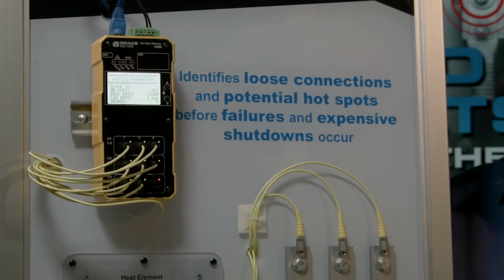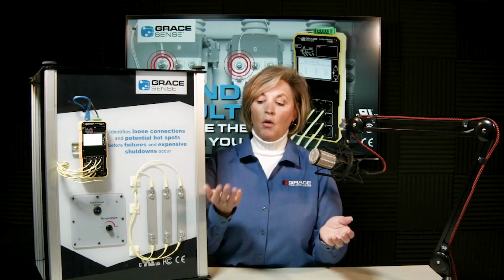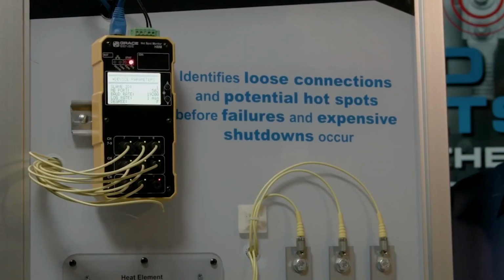Inside the module itself is an internal web page. And inside that internal web page, that's just pinged via an IP address, is where you would do all the setup for if you want to measure temperature in Fahrenheit or Celsius, or change your alarm set points. There are 2 levels of threshold, so you could say one section is for a more critical load, so you'll want perhaps a notification on a lower temperature, and the second set is maybe loads that aren't as critical, and you can raise or adjust those as needed. But the most important thing is to make sure that the alarm gets to the appropriate personnel and action takes place when necessary.